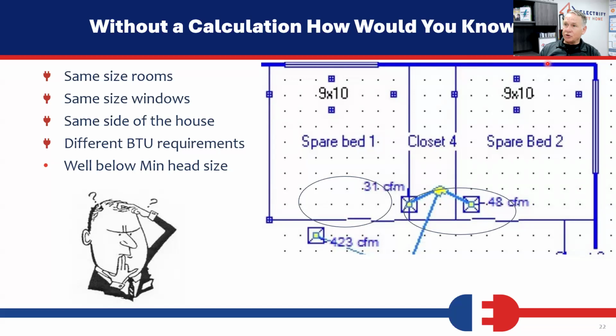Because if you haven't been doing load calcs for a long time, you don't recognize certain things that are reality until you've looked at it a bunch of times. And rooms that have 2 walls of outside exposure, like Mother Nature is existing on 2 sides of this room, it's only existing on one side of this room. I need less air in here, which equals less BTUs. And if you look at this small amount of air we need, that is way less than the minimum BTU head size of any system out there. So be careful.